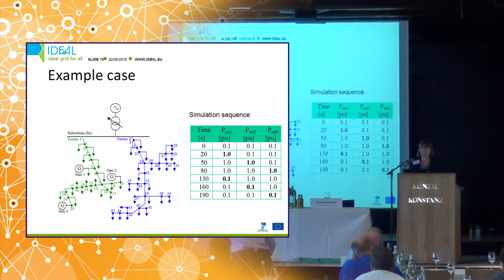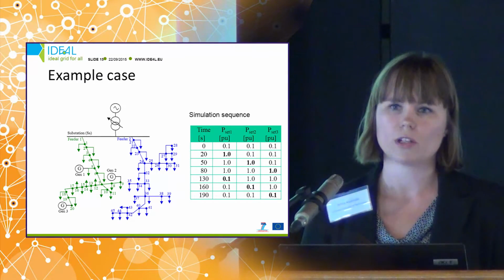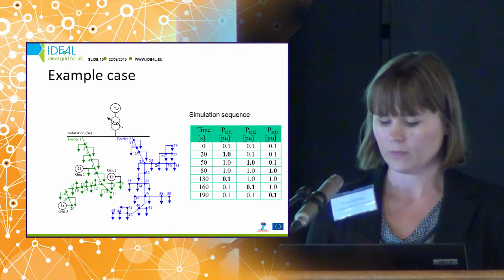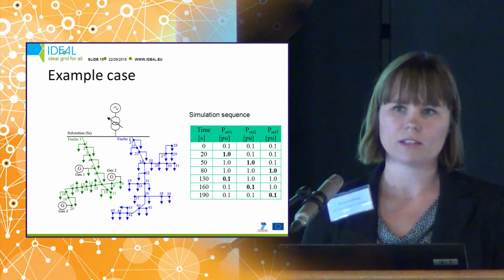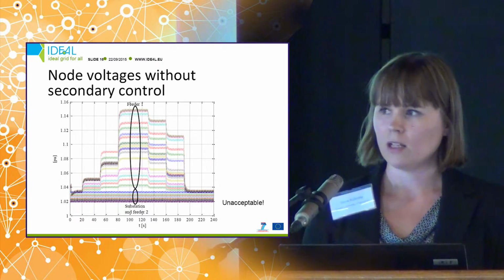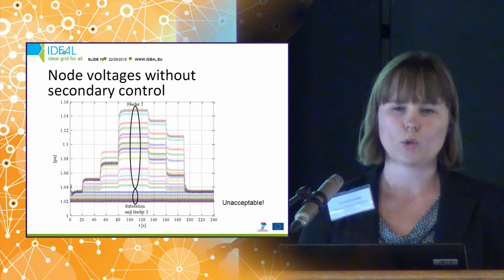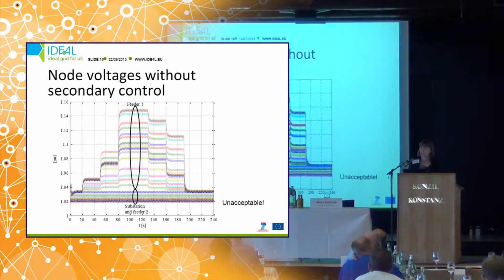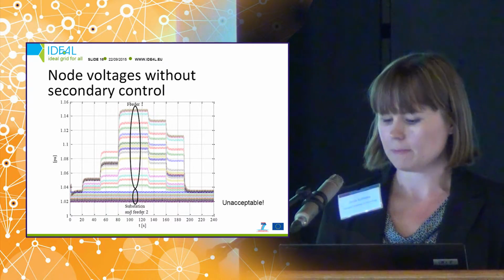At the end, I will show a short example case. This is a simulation done in PSCAD and MATLAB. And the network is in the figure. It has two medium voltage feeders, and one feeder has 3 generators and the other only load. And we first increase the generation and then decrease it one by one. This is how the node voltages would look like if we wouldn't have the secondary control there. As you can see, the voltage rise is quite large. This is not acceptable. So in this case, it would be possible to reinforce the network. We would need to build about 20 kilometers of new line. So this would be quite expensive in the example case.